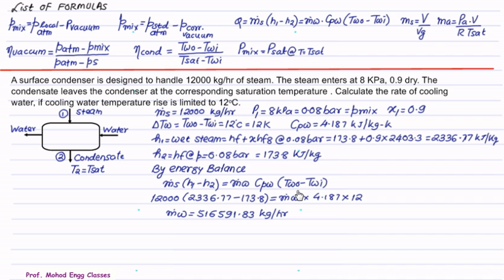Taking the energy balance, the heat rejected by the steam equals heat absorbed by the cooling water: Ṁs(H1 − H2) = Ṁw · CPw · (TWO − TWI). Substituting: mass of steam = 12,000 kg/hr, H1 = 2336.77 kJ/kg, H2 = 173.8 kJ/kg, CPw = 4.187 kJ/kg·K, and temperature rise = 12°C, we get the mass flow rate of water as 516,591.83 kg per hour.